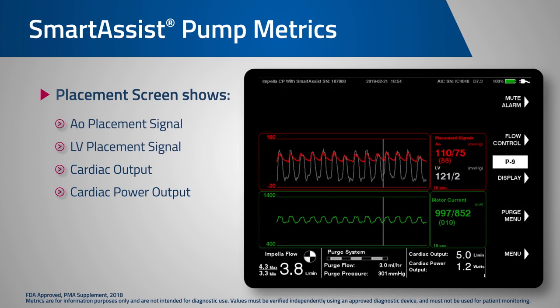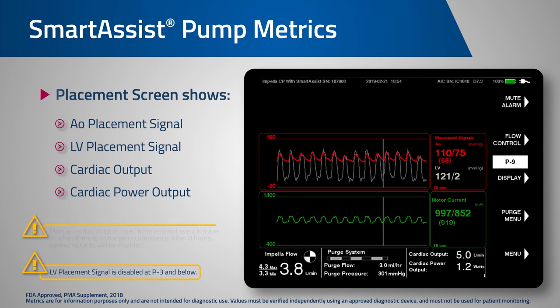The right lower box provides the total cardiac output and cardiac power output calculation. Today we will be focusing on the trending of these new metrics during weaning. Remember that the LV metrics are only available at P4 and higher and that cardiac output must be entered from a reference every 8 hours.